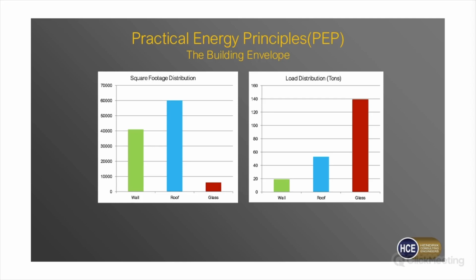So you can tell there is not a lot of glass square footage relative to the other two categories. But when you look at how much load comes from these three categories, it's interesting that the load distribution switches on you. Your glass makes up the largest amount of the load relative to the other two. Your walls make up the least amount, your roof is in the middle, and your glass is the largest load.